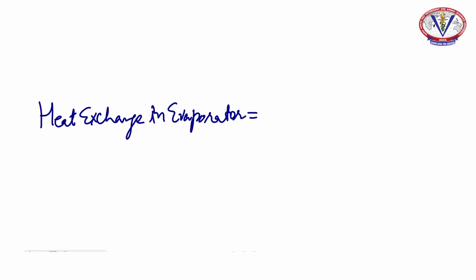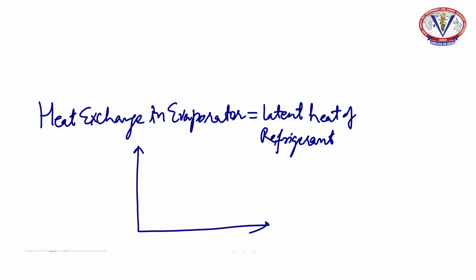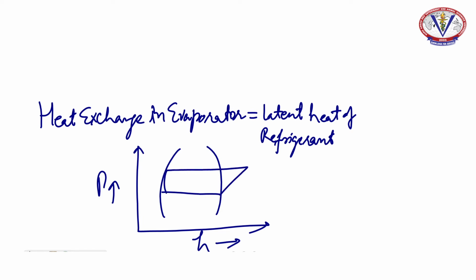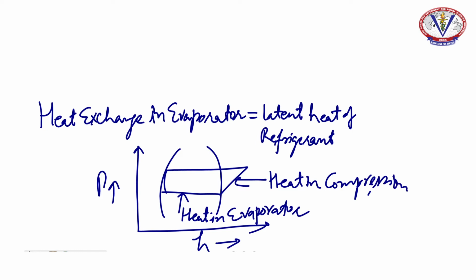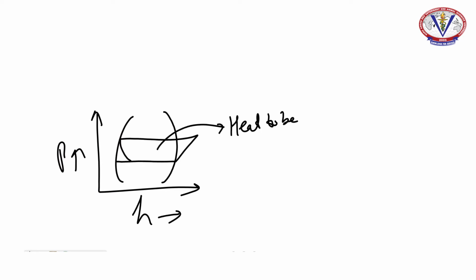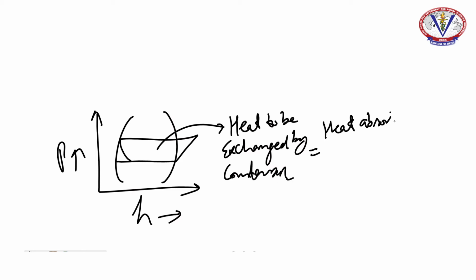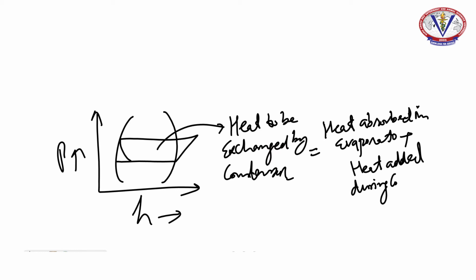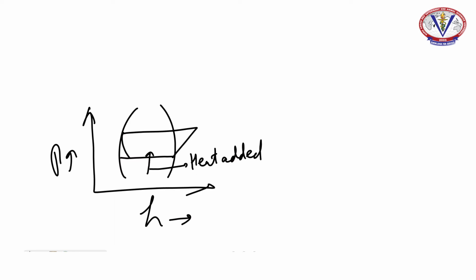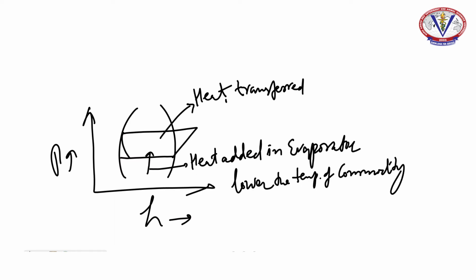In the evaporator, the heat exchange between the commodity to be cooled and the refrigerant is equal to the latent heat of vaporization of the refrigerant, whereas the same heat is sensible heat for the commodity side. In the condenser, the heat equivalent to the latent heat of vaporization of the refrigerant, and the heat added during the compression process, has to be delivered to the outside environment or to a suitable cooling medium. The condenser is shedding this total heat, that is the heat absorbed in the evaporator and the heat added during the compression process, to the environment. Now the heat being added in the evaporator is lowering the temperature of the commodity, whereas the condenser, which is shedding heat to the environment, is basically adding heat to the environment.